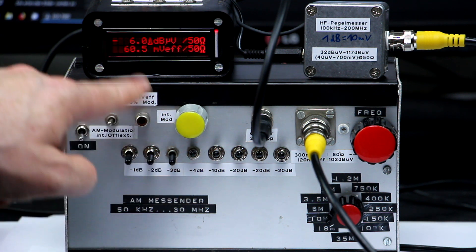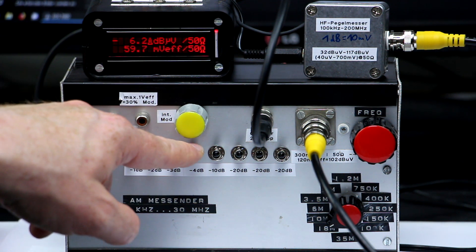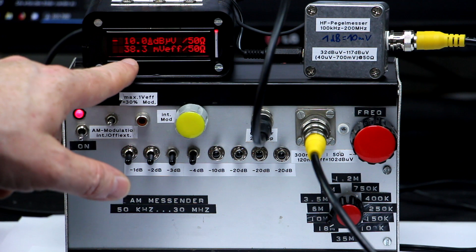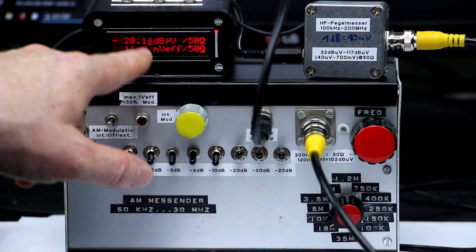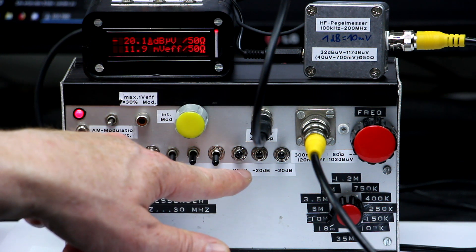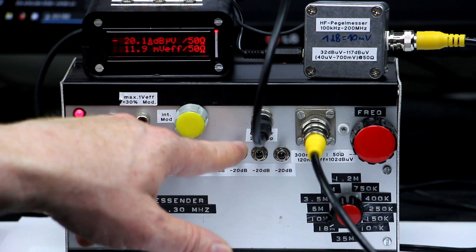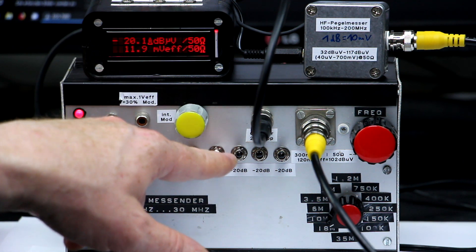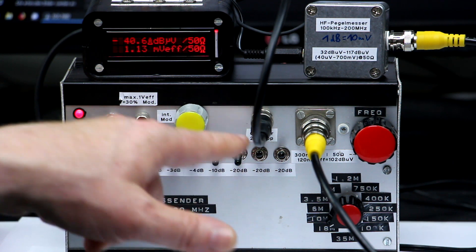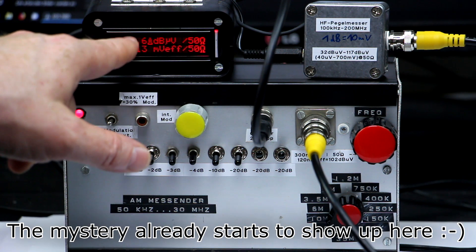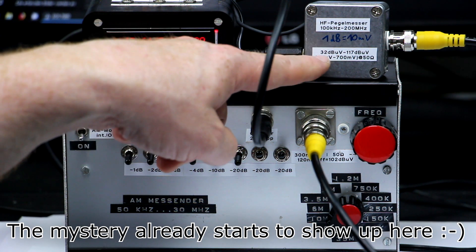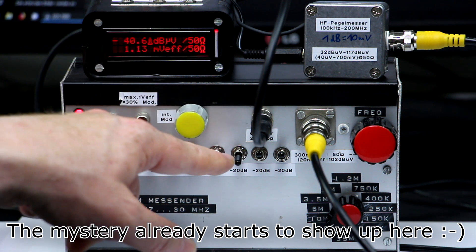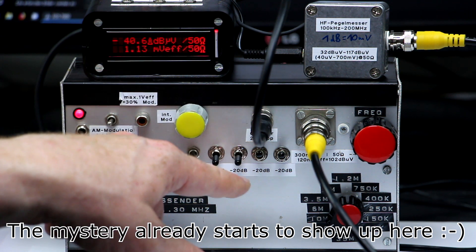Next one minus 4 dB plus the minus 6 should give minus 10. Yeah, we're exactly there. The next one minus 10 should give all in all minus 20. Exactly plus minus 0.1 dB. Then come the three minus 20 dB attenuators. The first one minus 20 dB added should give minus 40. A little bit less because we know they are not exactly minus 20 dB. So okay, minus 40.6 dB is within specs.